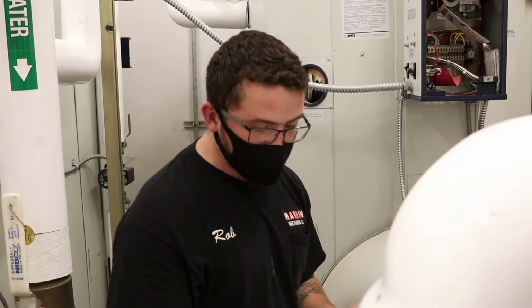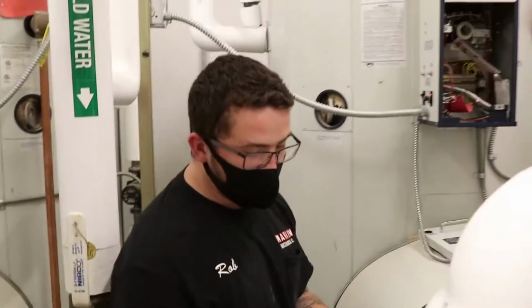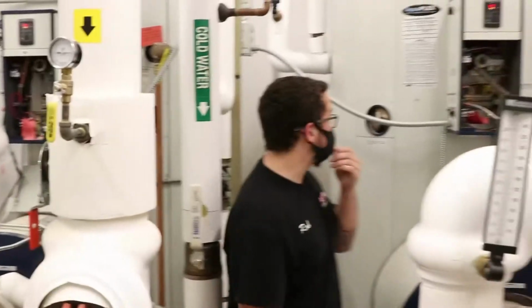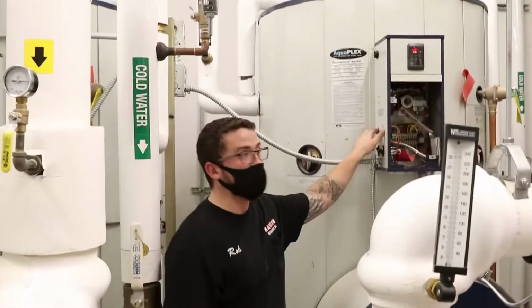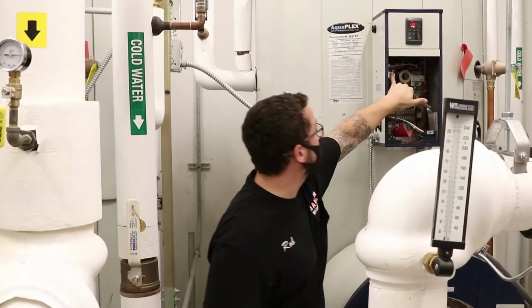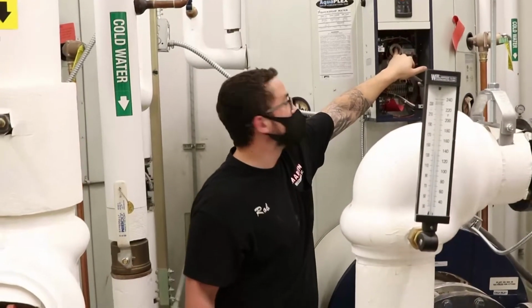So let's talk about maintenance now. Annually, you're going to want to check the safeties like we just discussed. Annually, you're going to want to test the low water cutoff. You're going to want to test the manual reset high limit. You're going to want to test the upper operating control.